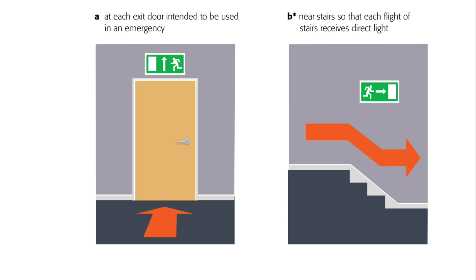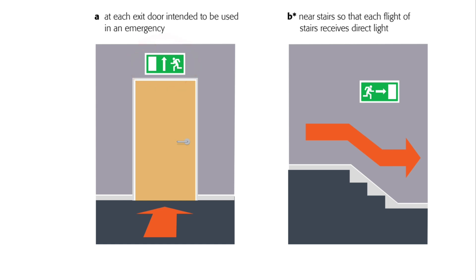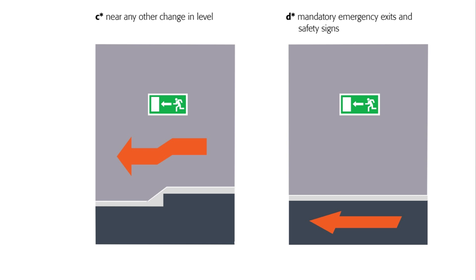It's interesting to note in the illustration that the arrow is pointing up — we're circling that all-important issue of which way signs should point. Near stairs, so that each flight of stairs receives direct light — this is important both so people go the right way and for safety at any other change in level. Wherever there's a step or change in level there's a chance someone could stumble if it's not illuminated well enough.